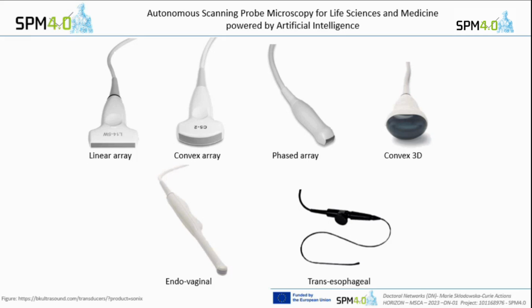Yes? Does it spread the image? Like when you're looking back, would it spread parts of the image along the axis? Yes, so it's spread. In a linear transducer, the lines of the image are parallel to each other. In this convex transducer, you have spread lines, so the distance between the lines increases with depth. So the image quality is decreasing, but you have this overview.